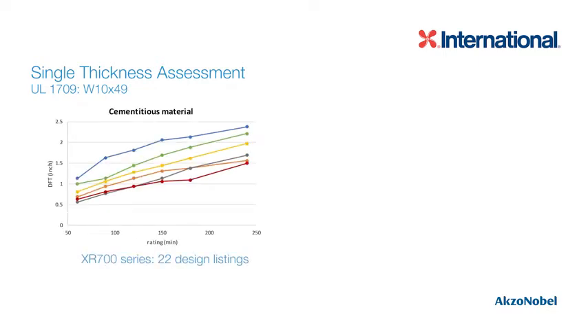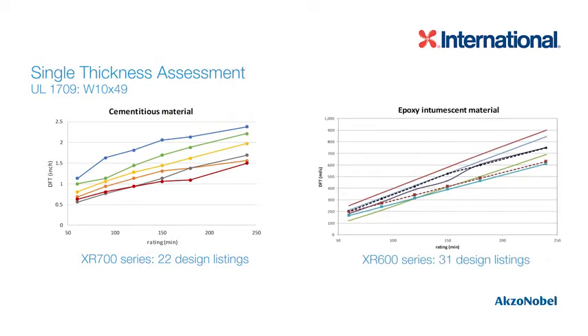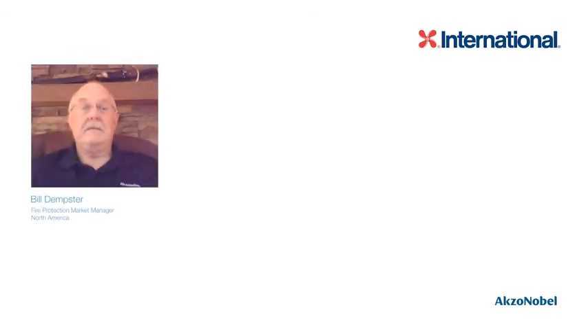If we look at the UL 1709 XR series designs, either the XR 700 series, which is for the cementitious material, or the XR 600 series, which are the epoxy and intumescent material, and I did not include on here boards or other types of passive fire protection material design listings. But you can see there are 22 design listings for cementitious materials using the single thickness approach, UL 1709 on a W10 by 49 piece of steel. So you look across at the hourly rating based on minutes, and you look up the dry film thickness, and that applies to the entire project. Same thing with the epoxy and intumescent. There are 31 design listings, and these go back as far as the mid to late 1990s. So in total, there are 53 designs.